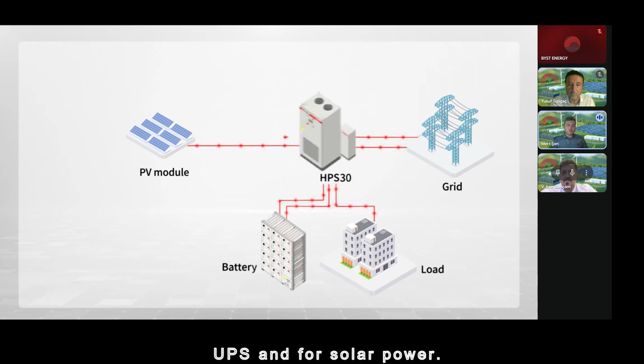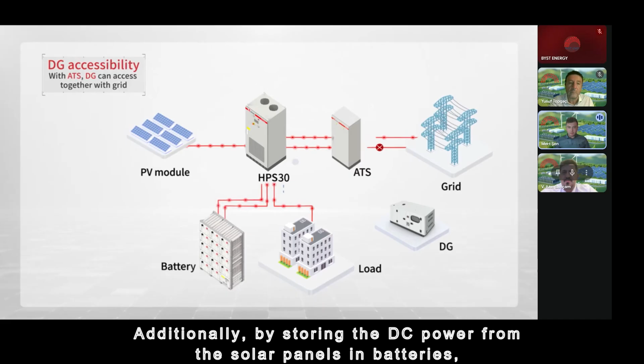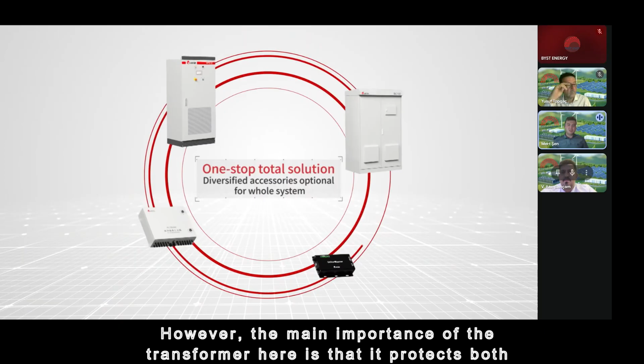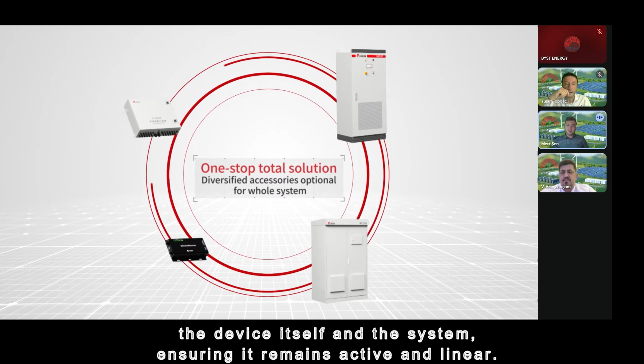With the hybrid inverter, we can use our product both as an industrial UPS and for solar power. We can connect this product directly to the DC bus and use it for self-consumption. Additionally, by storing the DC power from the solar panels in batteries, we can utilize the stored energy during peak demand periods, achieving higher efficiency and effectiveness. However, the main importance of the transformer here is that it protects both the device itself and the system, ensuring it remains active and linear.